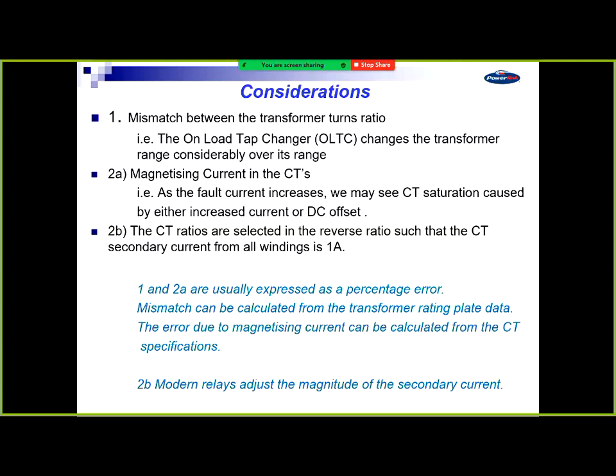Now, for the first two, you just get a percentage error, and we just put that percentage error in there, and that's how you set it. Then for the mismatch, the modern relays adjust for the magnitude current difference in the relays. In simple terms, you tell it what the CT ratio is, and it multiplies that by the current it's getting from the secondary, so it knows its primary current. So it can be any sort of ratio.